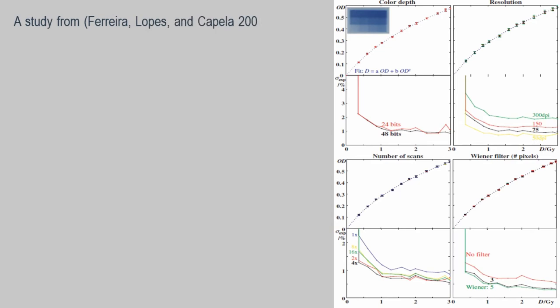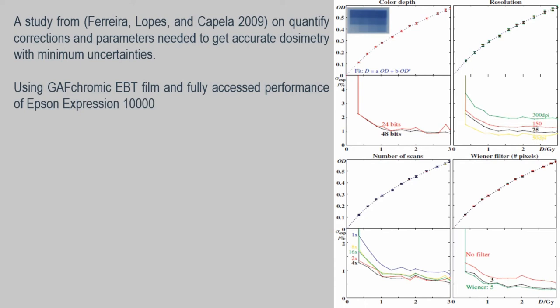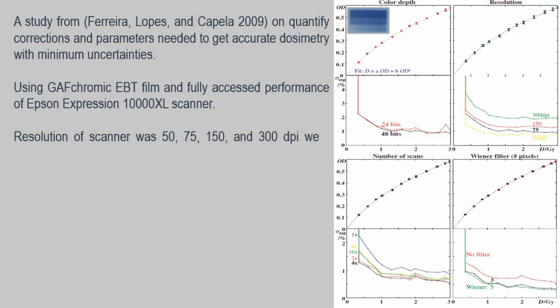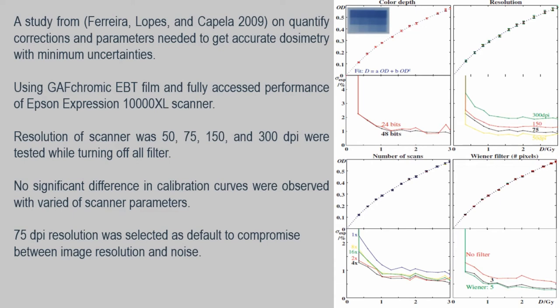A study from Ferreira, Lopes, and Capela in 2009 was done to quantify corrections and parameters needed to get accurate dosimetry with minimum uncertainties. It was done using GAFChromic EBT film and fully assessed the performance of the Epson Expression 10000 XL scanner. Resolutions of 50, 75, 150 and 300 dpi were tested while turning off all filters. There was no significant difference in calibration curves with varied scanner parameters. It was concluded that 75 dpi resolution was selected as default to compromise between image resolution and noise.